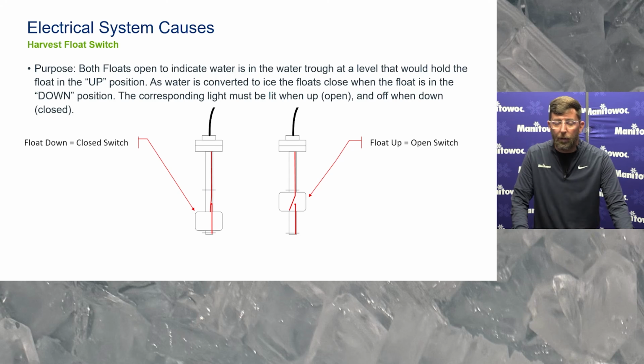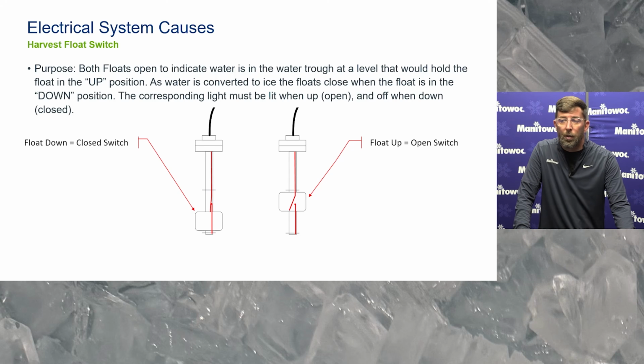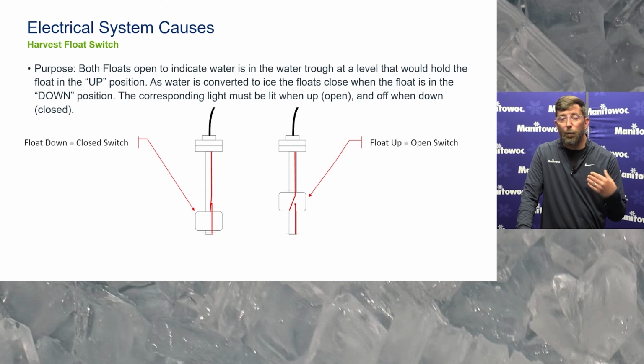So we have 2 floats. The purpose of these floats, when they're up, it creates an open circuit to let us know that water is up to the level of the corresponding float. The one on the right is showing that it's up, and it would create an open circuit and the light on the control board would be lit green. If it's down, it creates a closed circuit and the light on the control board would be off.